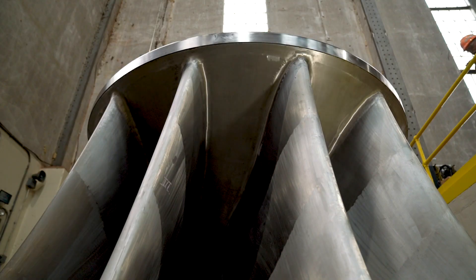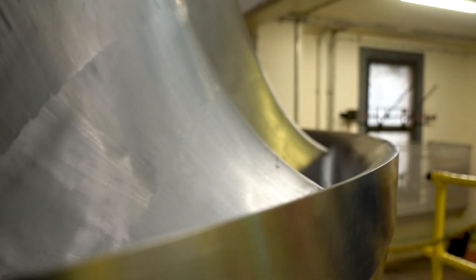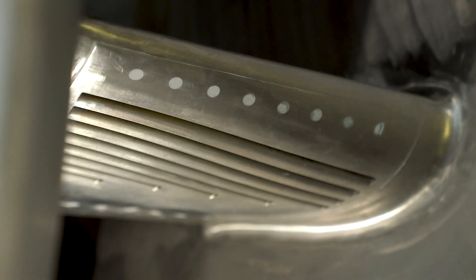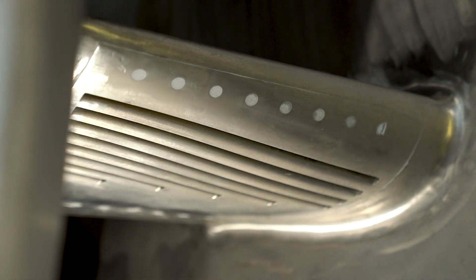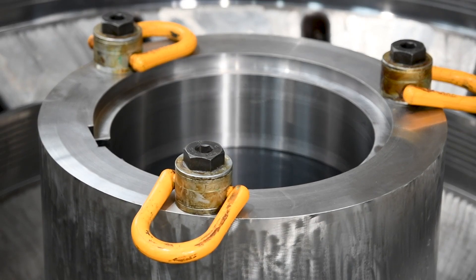The nice thing about our design is that we basically keep a standard turbine design for the regular runner blade, and the only thing we really have to compromise on — and it's not even much of a compromise — is we have to make sure there's enough space in the thickness of the runner blade itself to have an air channel that's going to take the air from the air end down to our interblade profiles.